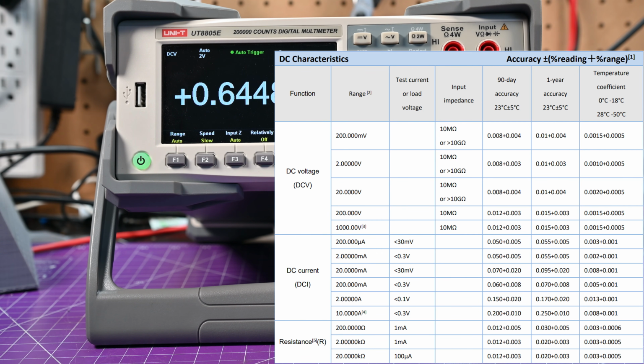Just to give you an example, in the 20 volt range, at the 90-day range, it's plus or minus 0.008% of the reading plus 0.004% of the range. And for the 1-year rating, it's 0.01% of the reading plus 0.004% of the range. So I'll let you go check that out yourself, link in the description.